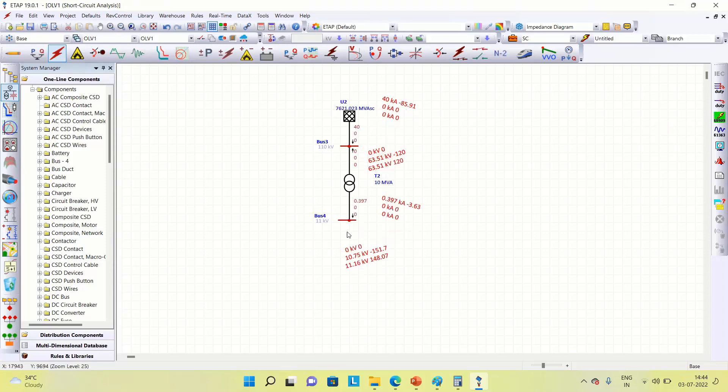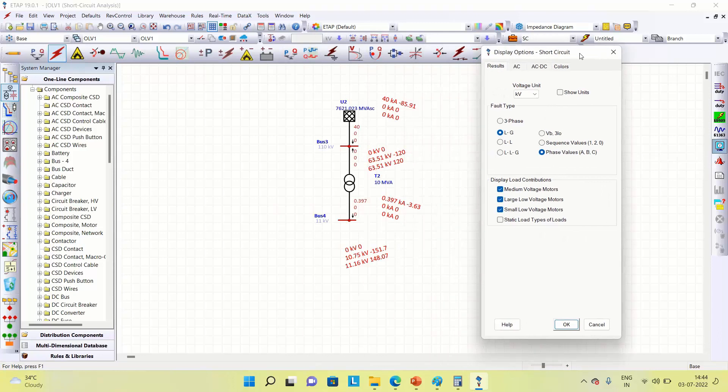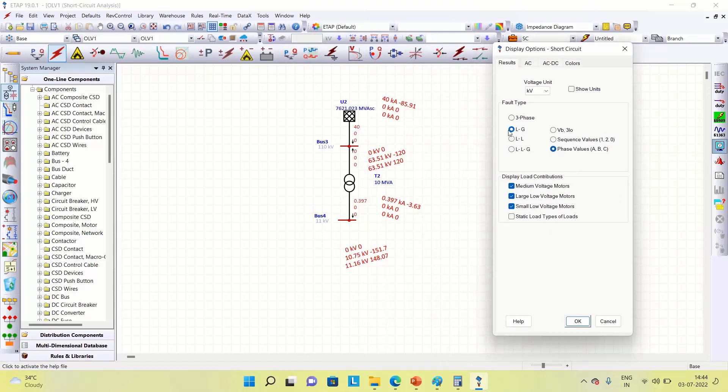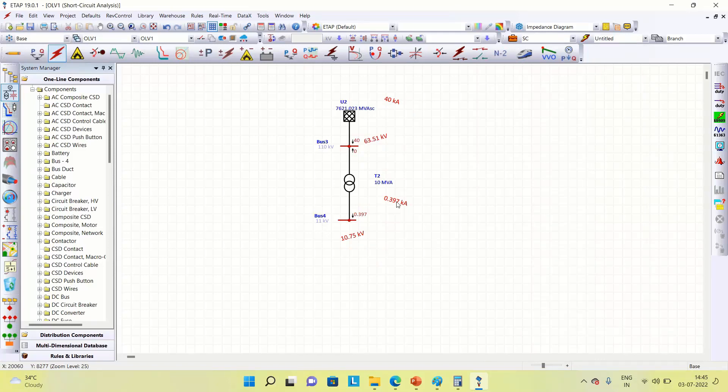Now we can see the fault current at LV side is 0.397 kA. Let us see what kind of fault this is - line to ground fault, okay.